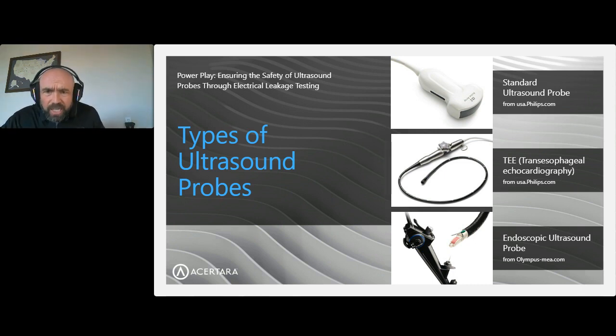Let's see. So Jesse asked, the leakage testers for specific probes have a set limit by manufacturer. That's generally accurate, right? The TEE probes, and all probes, you have an instructions for use document that comes with those probes. They're available for anybody to download. You don't even have to own the probe. You can go do your own research to get information for those. But those instructions for use, or IFUs, they're also supposed to have in them the specific electrical leakage limits for those transducers.